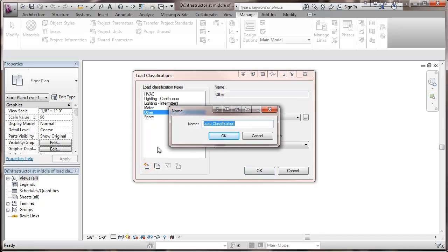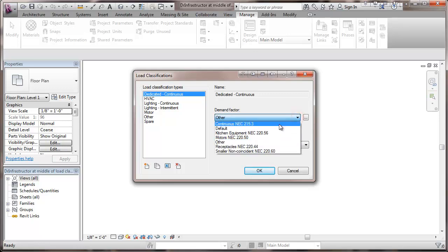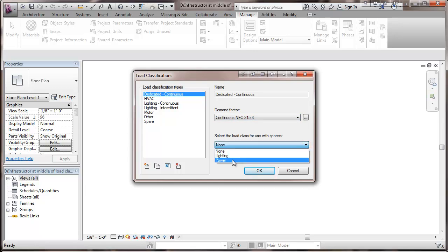And now I'm going to add a new one. I'm going to call this one dedicated and continuous. This would be equipment. The only thing on the circuit is a particular piece of equipment. And this equipment would be something that runs all the time. So you can be running more than three hours at a time. So for this we're going to go to our continuous demand factor. And I'm going to assume that this is going to be power equipment.